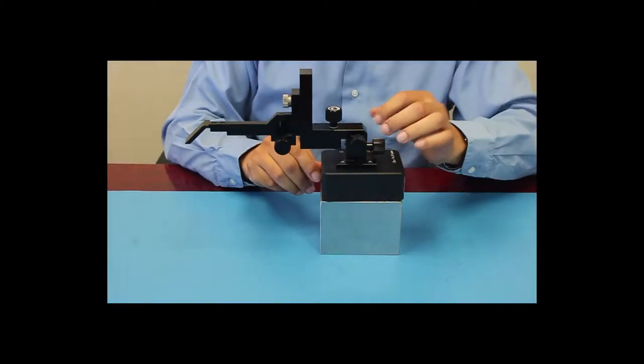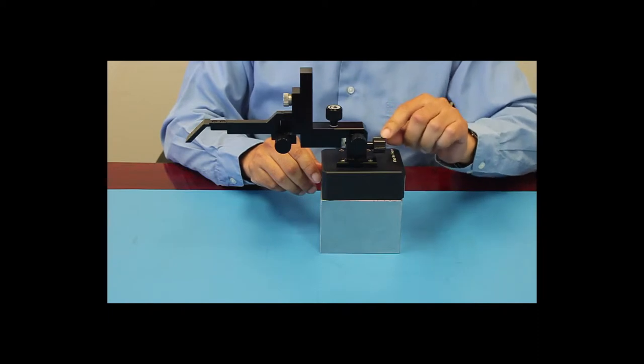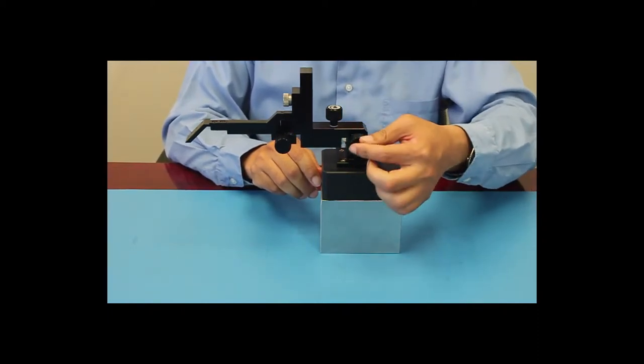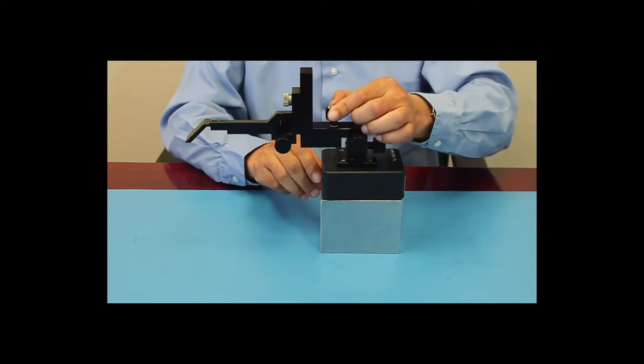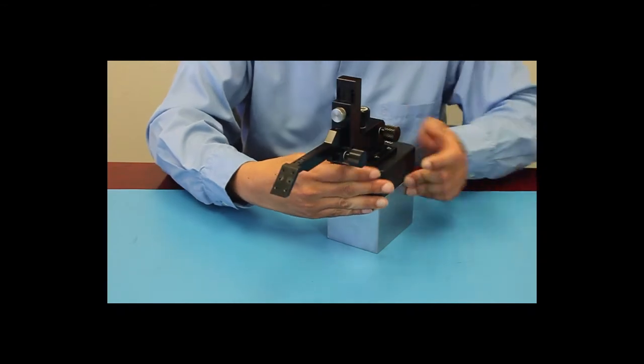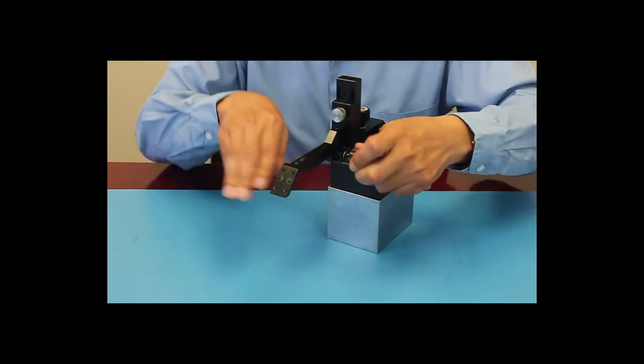This is the XYZ stage of the probe arm. X controls the front and backward movement, Y controls the left and right directions, and the Z screw allows up and down movement. Each stage can be moved 500 microns per turn. There's also a theta control on the side that maneuvers the lateral position of the probe tips.